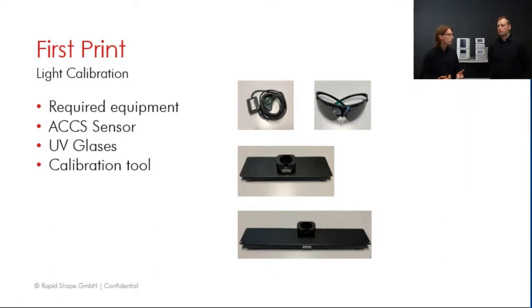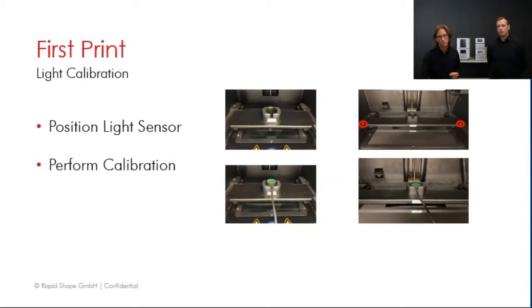The required equipment is the UV light sensor, which comes with the machine, same as the UV glasses, and the calibration tool. You might see that the calibration tool looks a bit different from machine class to machine class, but in the end you just insert it into the machine, you connect the sensor to the printer and put the sensor into the calibration tool. Let's take a look at how this is done.